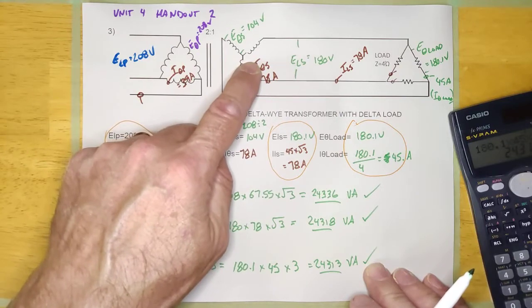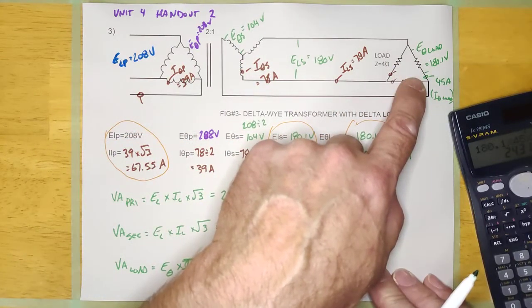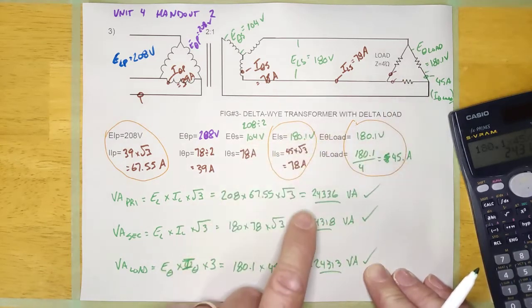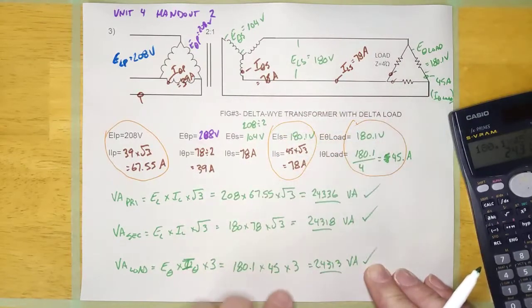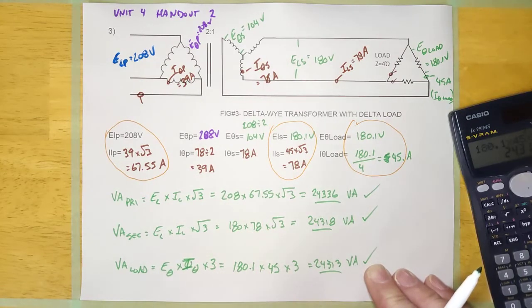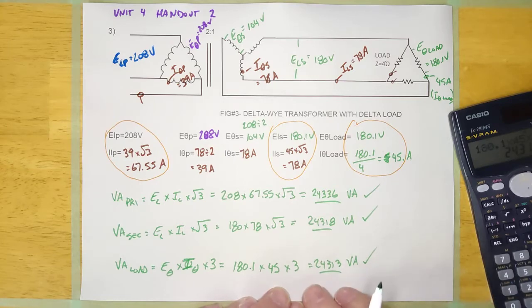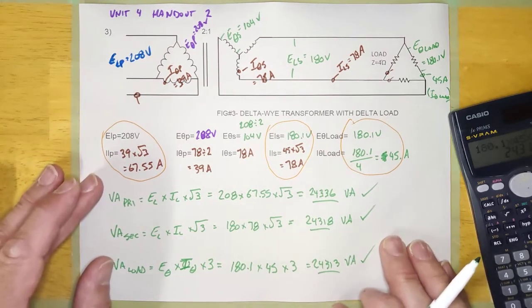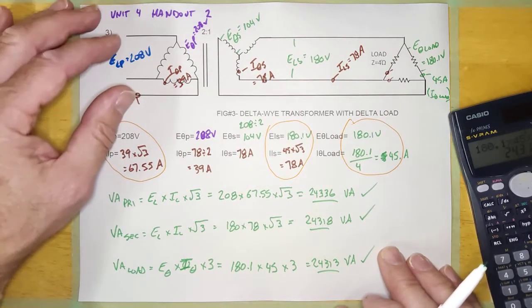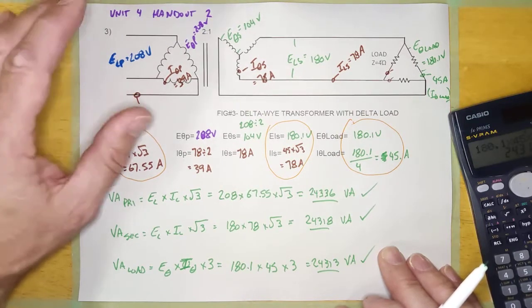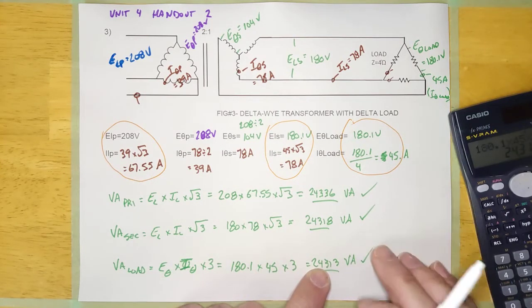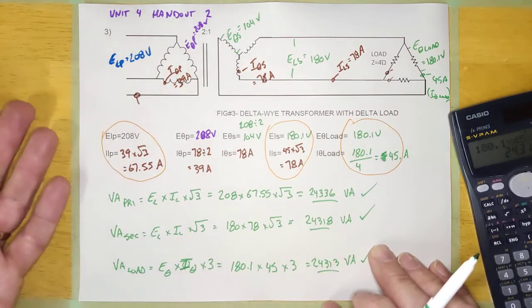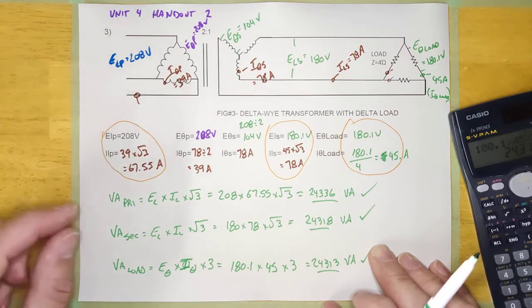The Van Andel way: line values to calculate VA at the primary, line values to calculate VA at the secondary, and phase values to calculate VA at the load. Why not line values at the load? Because the line values coming out of the transformer are the line values going into the load, so you'd just be recalculating the same numbers. By using phase values at the load you're actually checking something different.